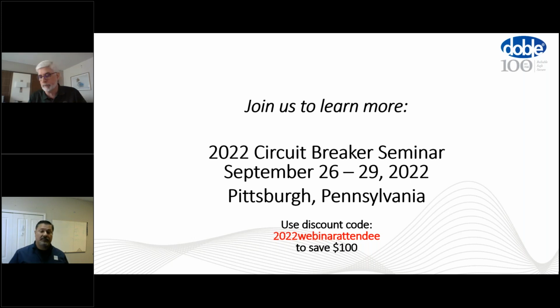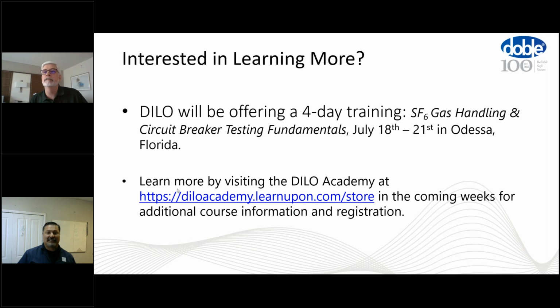Oh, thank you. So yes, there are. The different standards, whether you're looking at IEEE, IEC, or CIGRE, have references to SF6 gas in service. So there are limits. For example, you could see up to 500 ppmv of SO2 in a breaker in service. Obviously, if you're introducing new SF6 or you've recovered SF6, you want to scrub all that SO2 out of it, but there are limits. Generally, you'll see everything between 12 ppmv in some standards, and then some OEMs and others adopt 500 ppmv of acceptable contamination in service. Okay.